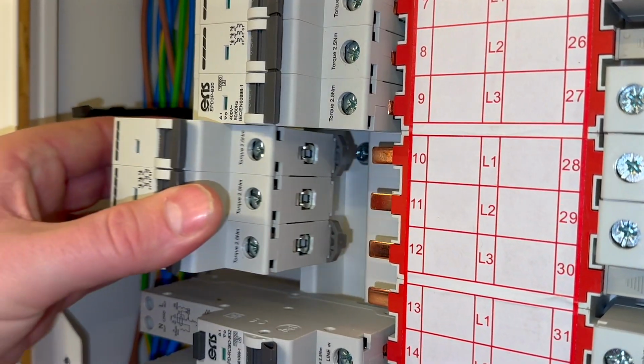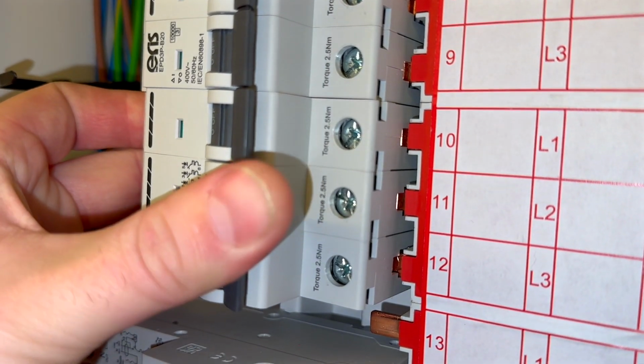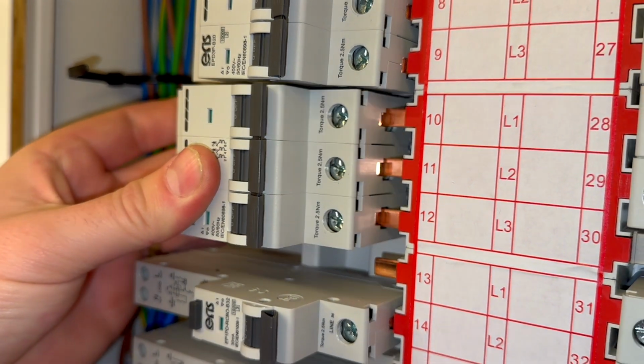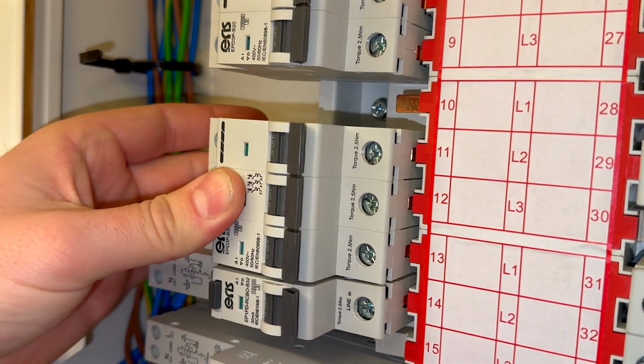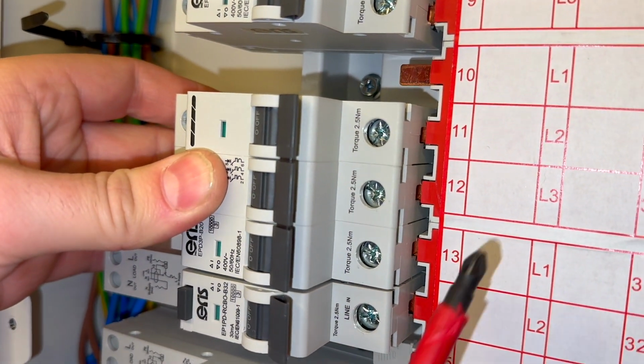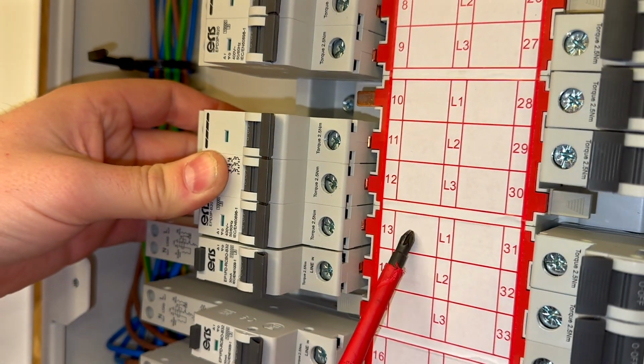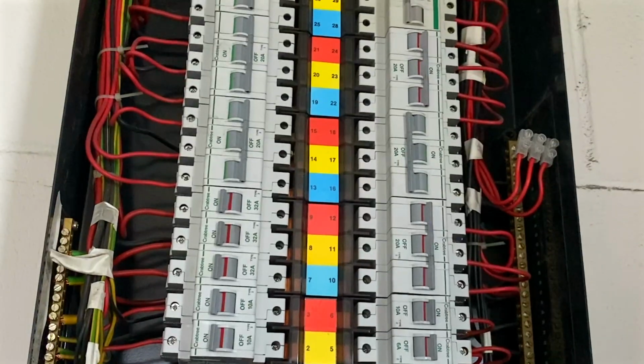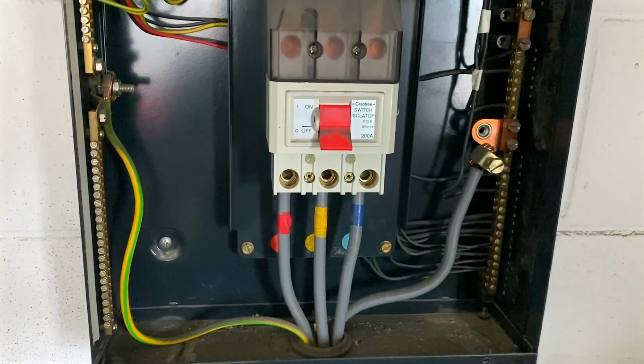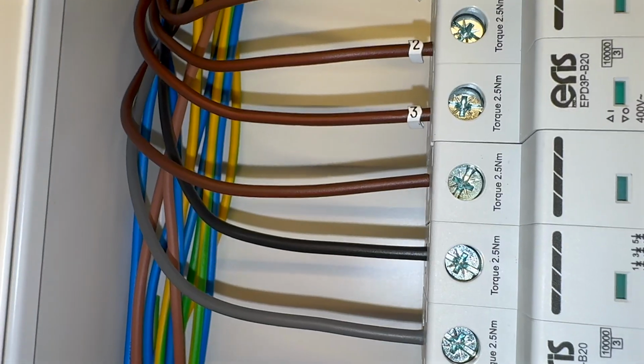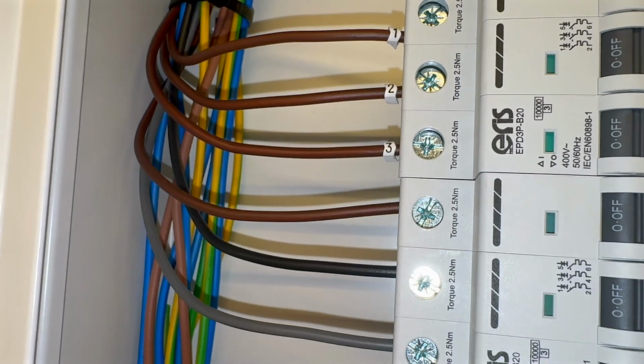To mitigate this, it may be wise to space out devices or position them next to circuits with lower continuous loads. For 3-phase devices, it is considered best practice to follow a logical sequence of L1, L2 and L3. However, it is possible to install devices that do not adhere to this sequence, which could inadvertently cause phase rotation. Be mindful of a few key details, especially the wiring colours. If you're like me and have been around long enough to remember, the old phase colours, red, yellow and blue, were much easier to identify. Unfortunately, with standardisation, we now have brown, black and grey.